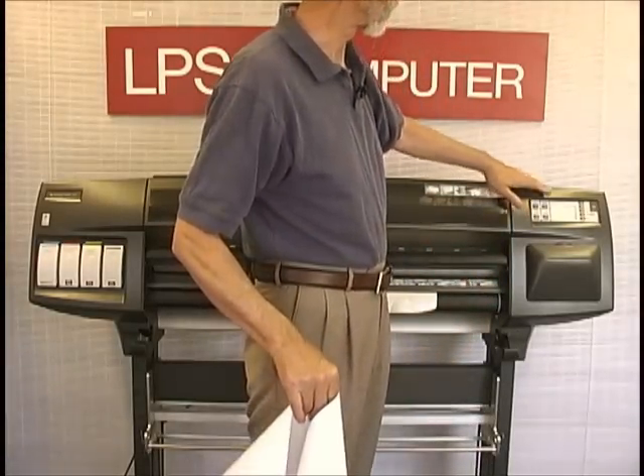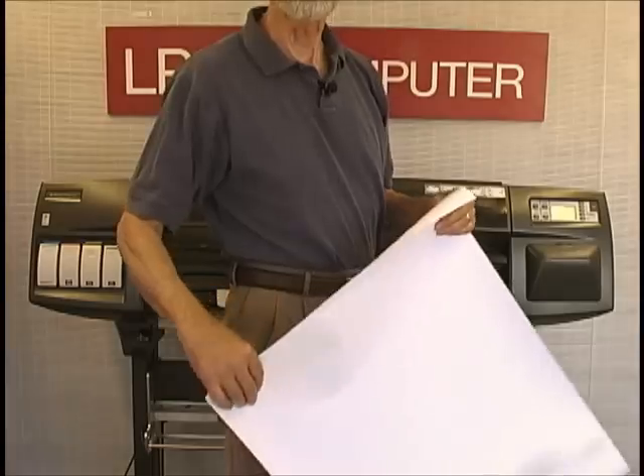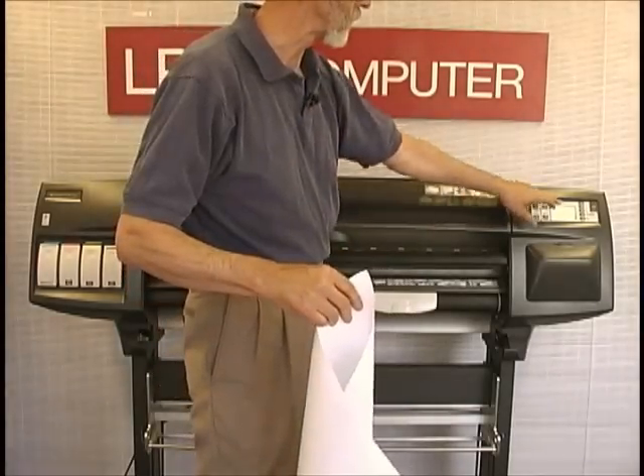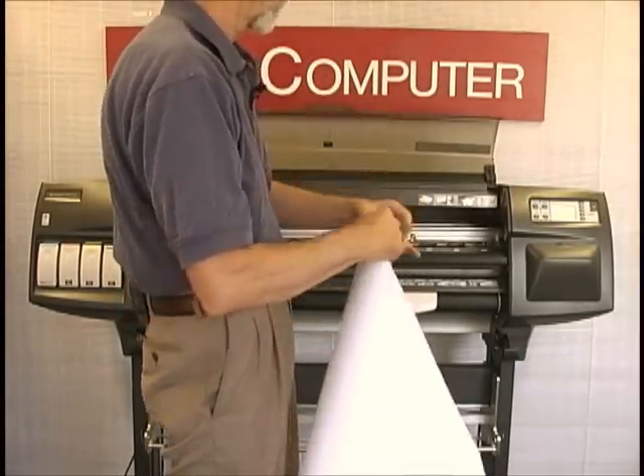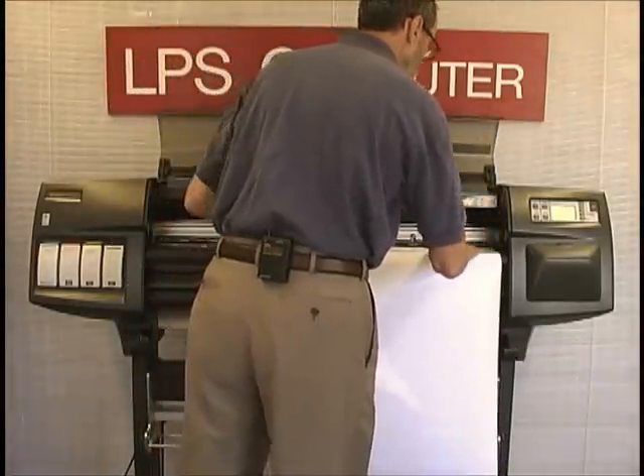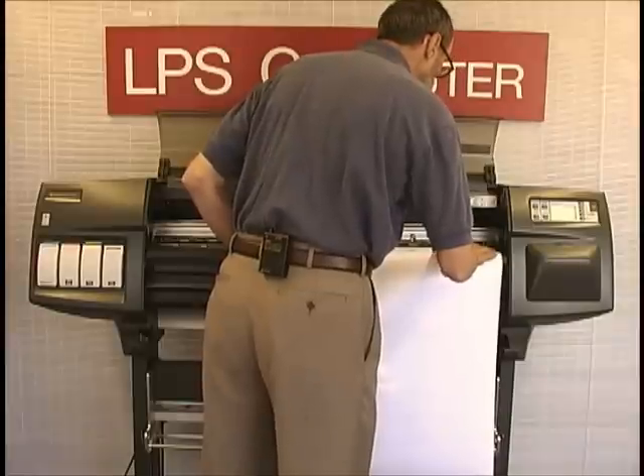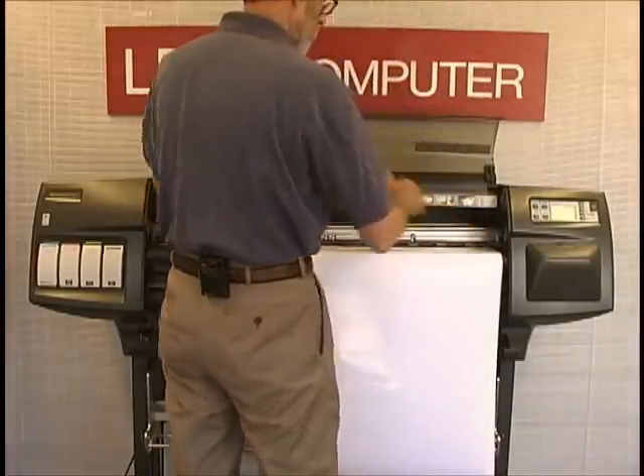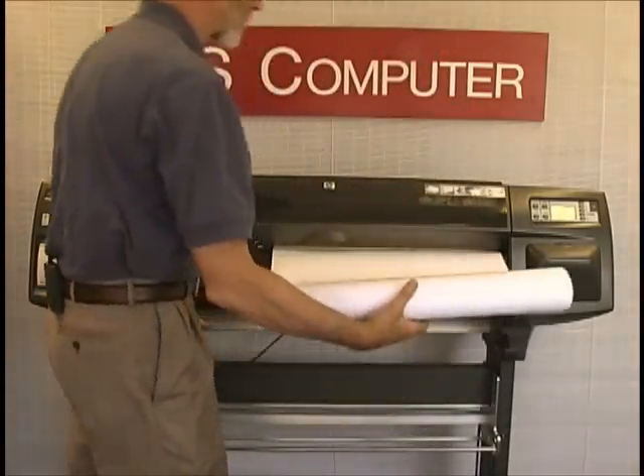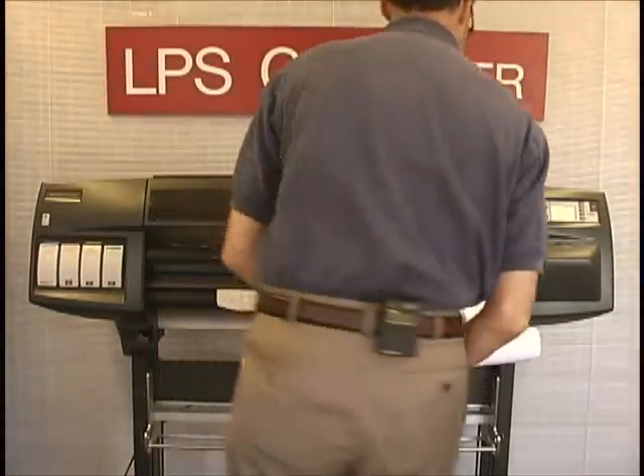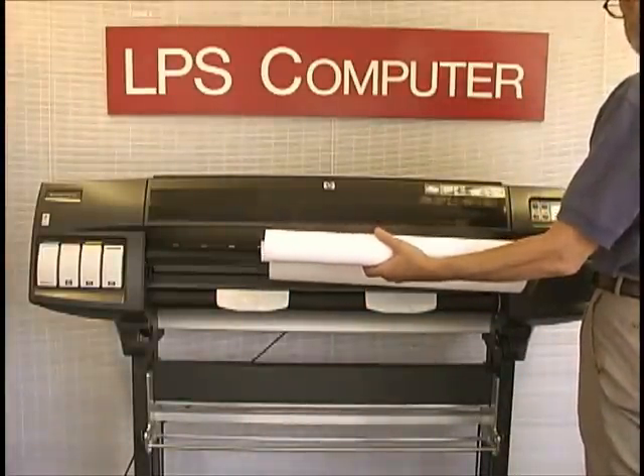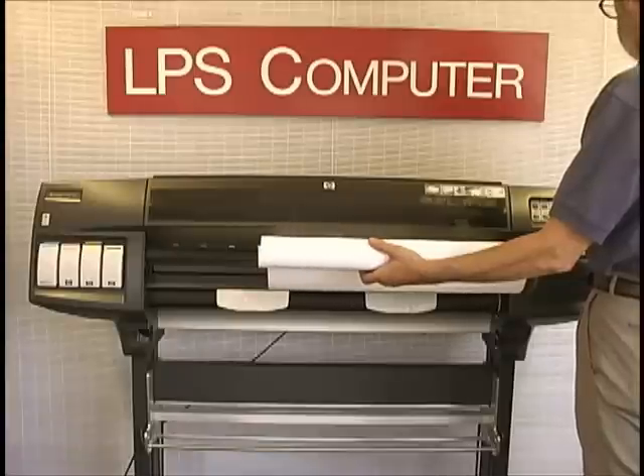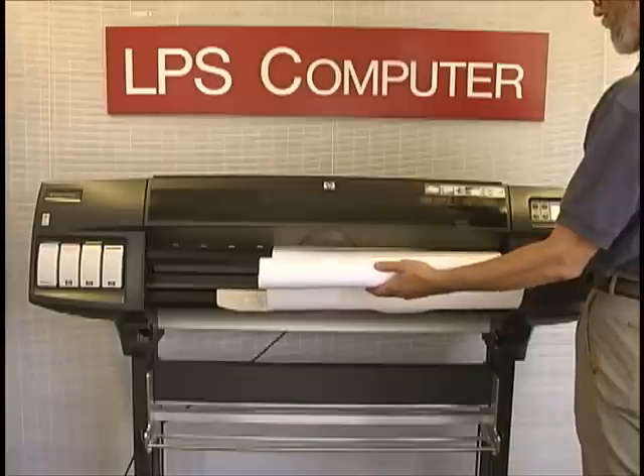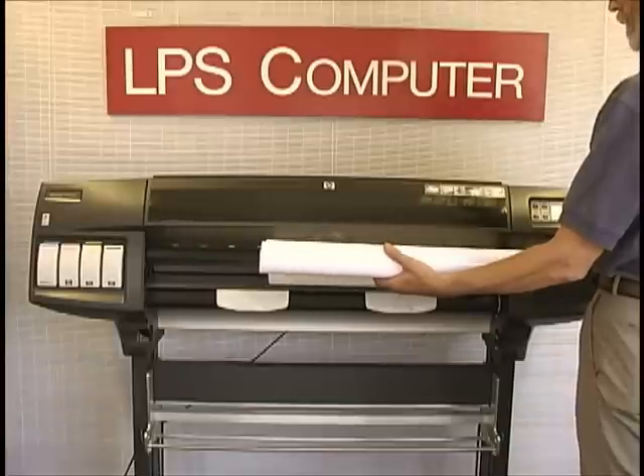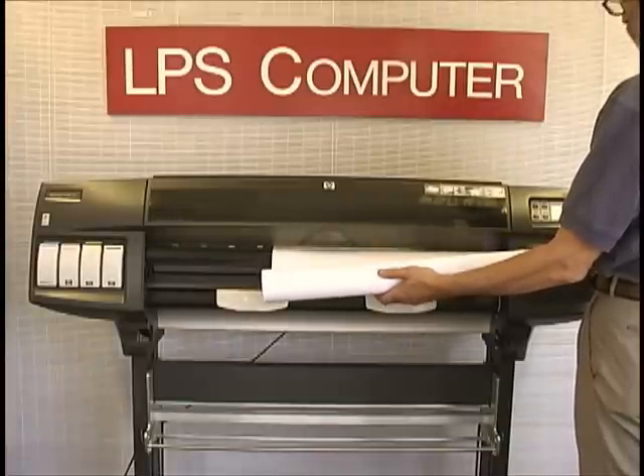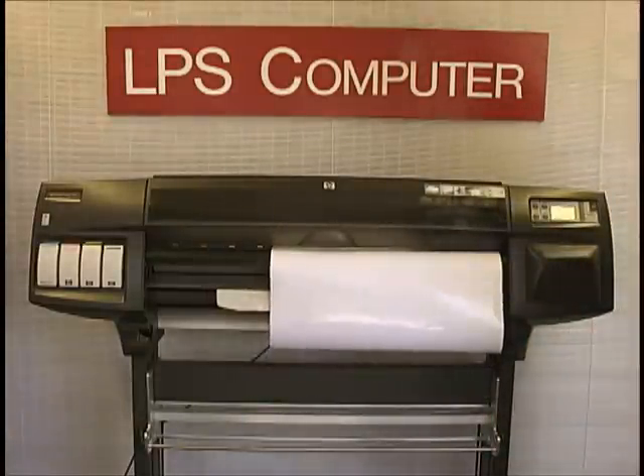Okay, the machine has gone through its initial testing and calibration for the accuracy adjustment. Next thing we're going to do is load the paper. The display is asking for sheet, so we're going to give it a sheet. Line it up with the blue lines there, and we'll bring it down. It's a little bit stiff. You may want to hold it up like this to help it load. I'm going to tell it that this is high gloss photo because that's the finish that's on it. It'll lay down the proper amount of ink as a result of that. Once the rollers pick this up, I can let go. Okay, it should handle everything just fine from there.